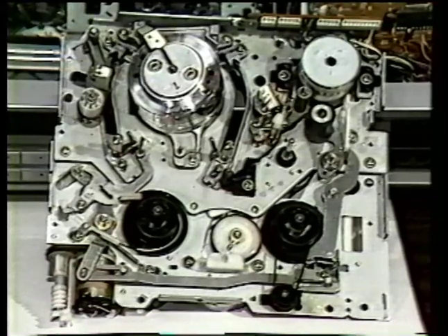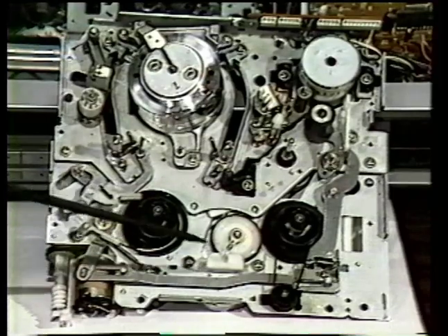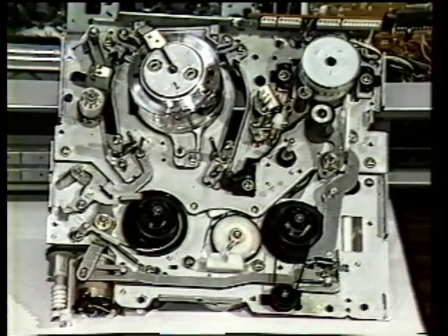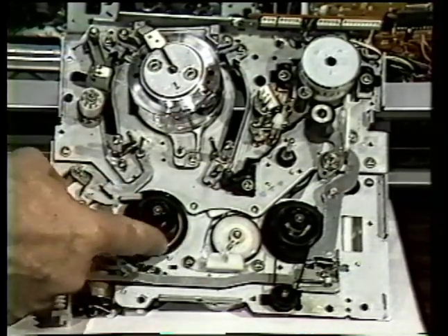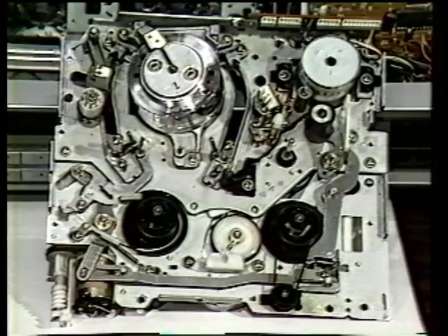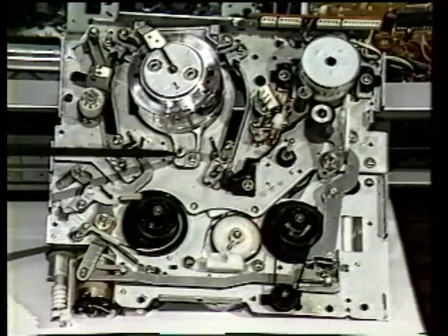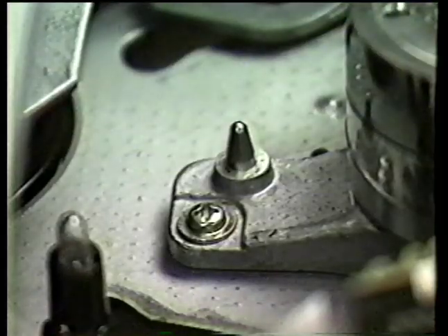Whether the machine is a top load or a front load, there will be a supply spindle and a take-up spindle mounted pretty rigidly in the machine. As you can see here, it's mounted to the base plate itself. The cassette housing is supported by 4 locating pins, one located here that you can see has a little taper on it, another little taper pin here.